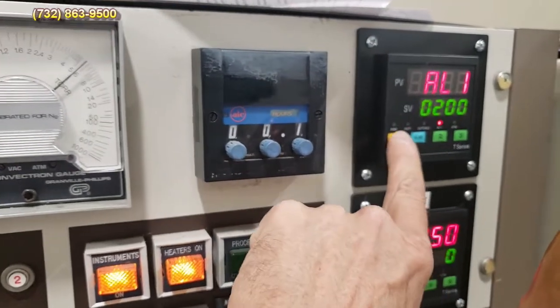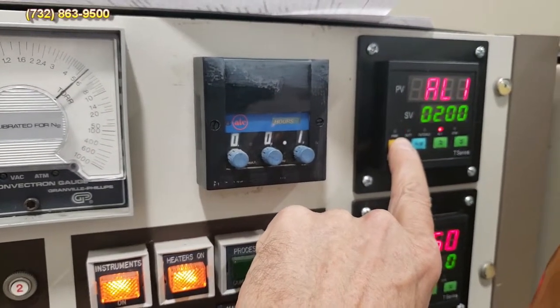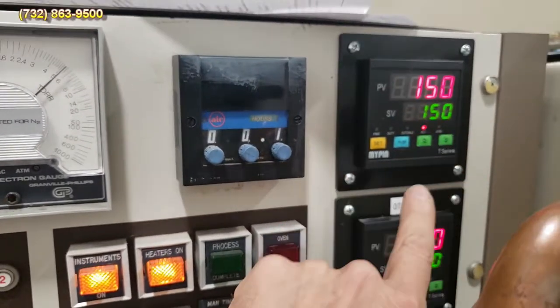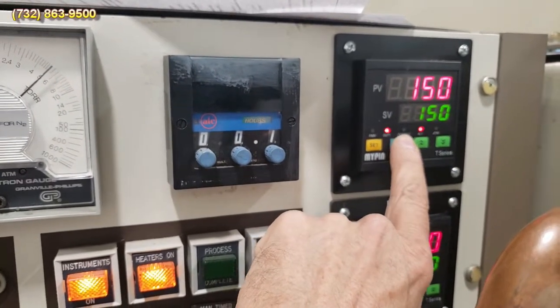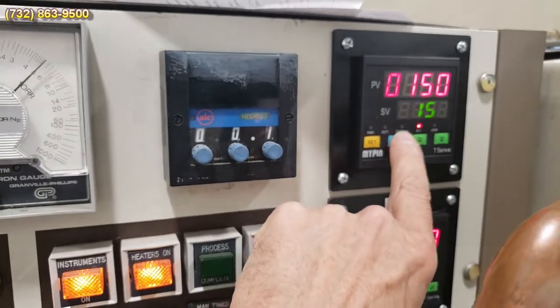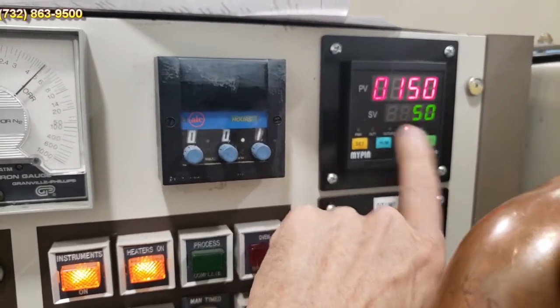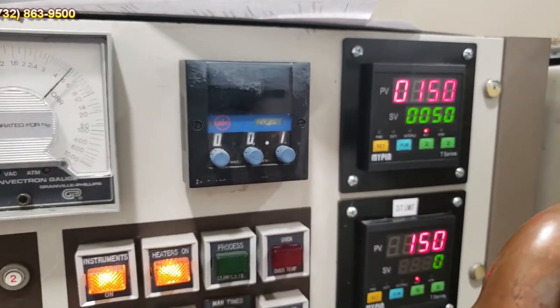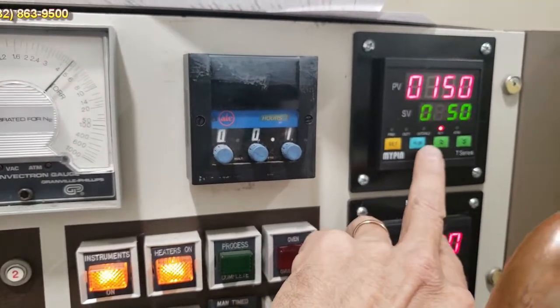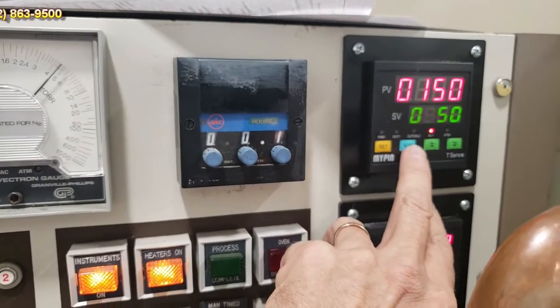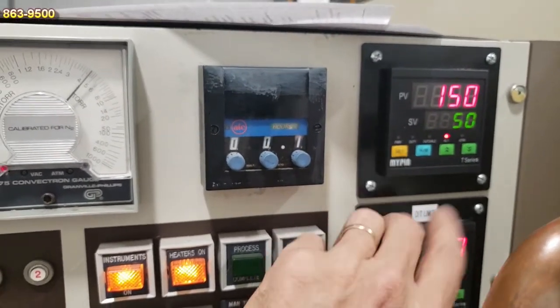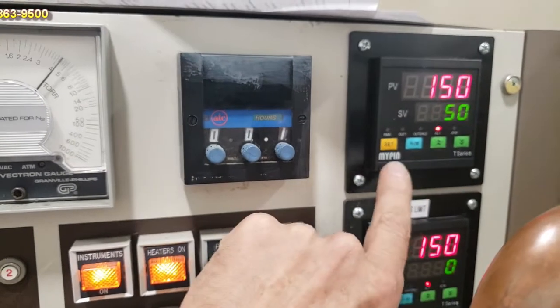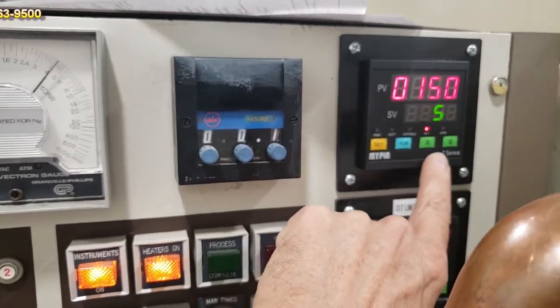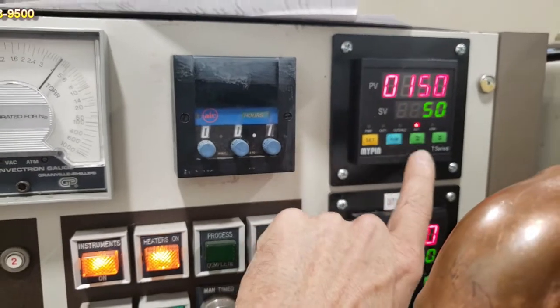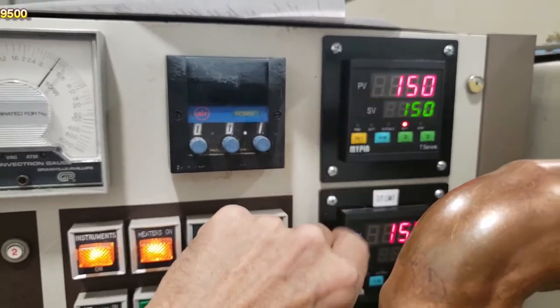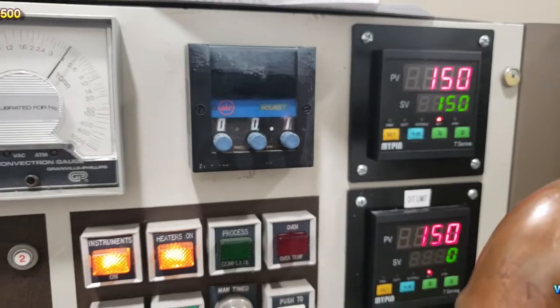So once you get that, you hit set again. It'll bring you to the temperature. If you want to change the temperature, you just go ahead and hit the blue button once so you can see that the number changes as you go across. If I wanted to bring it down to 50, for instance, you can go ahead and change it there. And then go ahead and hit set. And as you can see, the set value is now changed to 50. So let's go back and change that to 150. Again, hit the blue button. And 1 second.